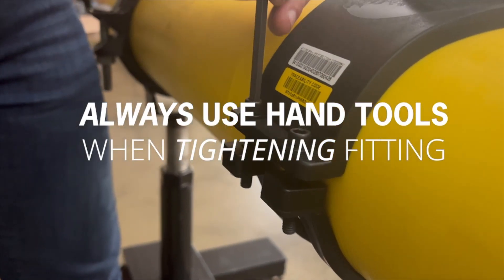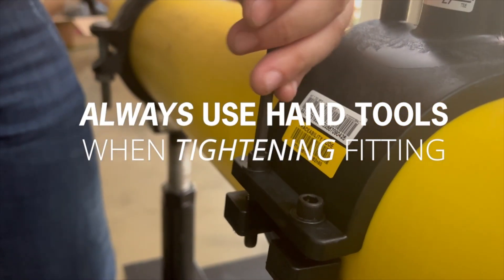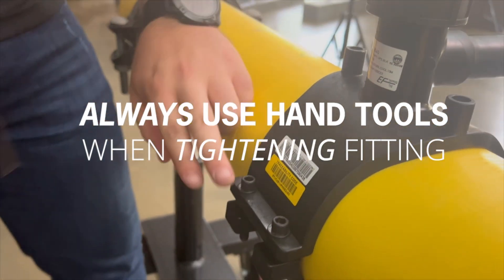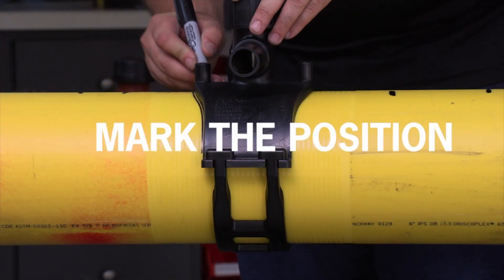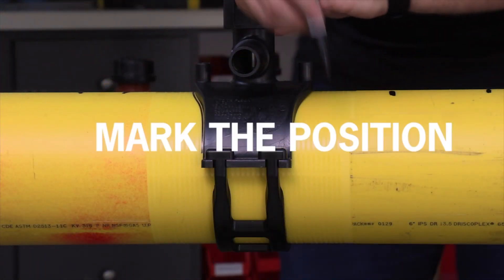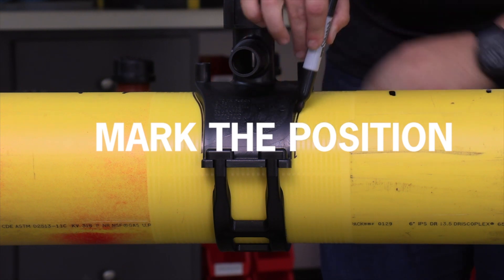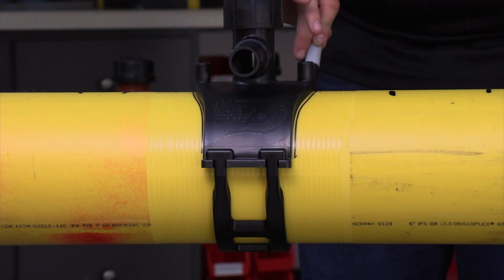Always use hand tools for tightening, never electric or air tools. After the tee is tightened on the main, make another set of witness marks along the base of the saddle. These marks will give a visual indication that the tee isn't moving out of position during the fusion process.